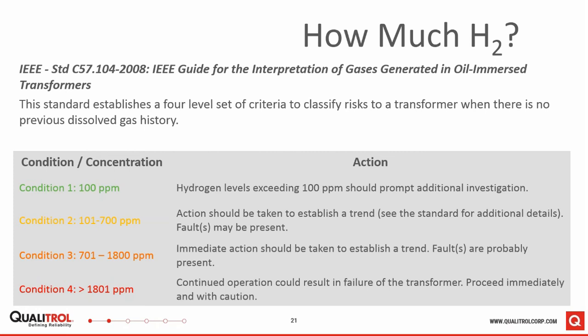But I have talked to Dr. Michel Duval, one of the foremost world leaders on DGA analysis, and his comment when I asked him about DGA and small transformers versus large transformers is that in general, these guidelines apply to any size of oil-filled transformers. So from a statistical standpoint, he has not found that small transformers generate significantly more gas than large transformers on a parts per million basis. That if you have 50 ppm of hydrogen in a small transformer, that is going to be pretty much just as significant as 50 ppm of hydrogen in a large transformer.